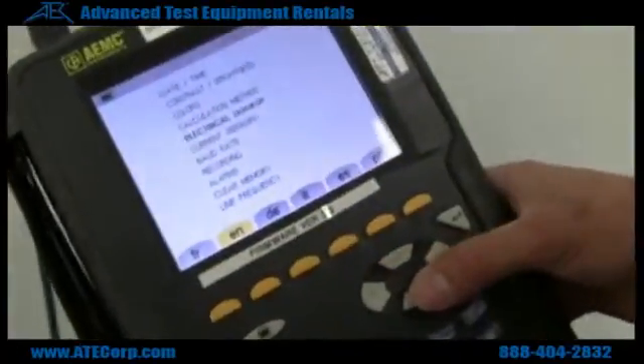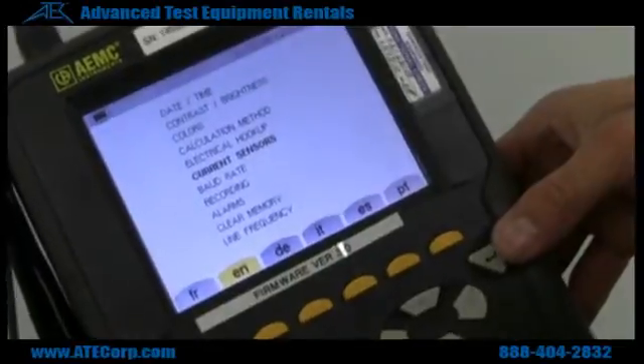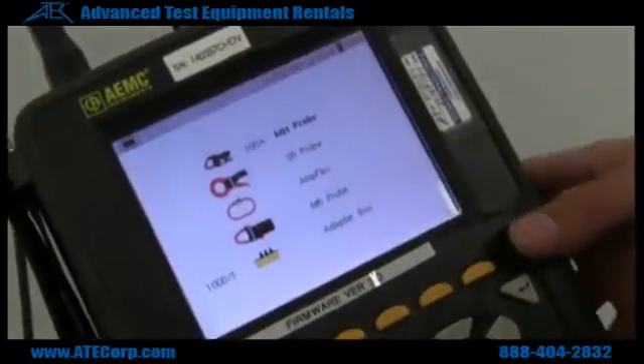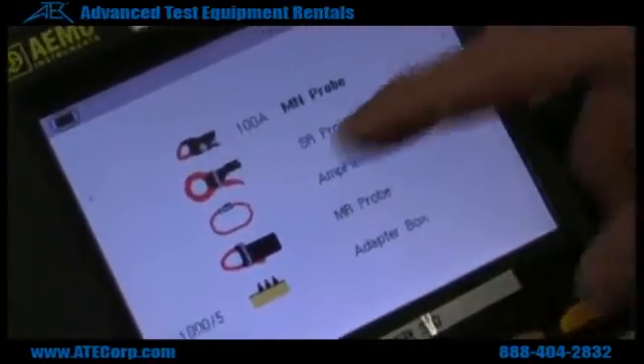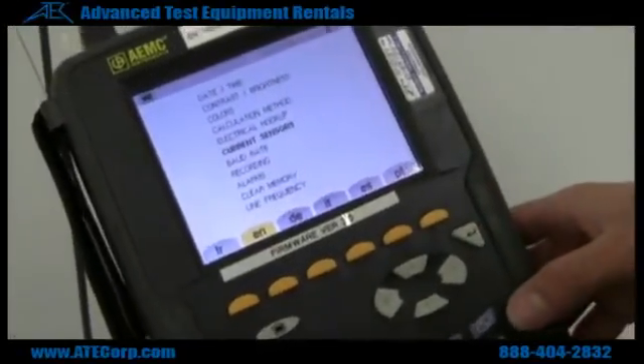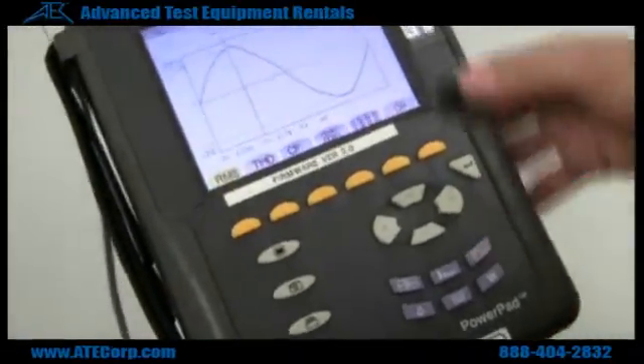After I do my electrical hookup I want to check my current sensors. Most of the time the AEMC 3945 recognizes what current clamp you have on it, but just to make sure you always want to check. In this case we have the MN probe, and we have it set for the 100 amp range, and it's highlighted so I have the correct setting on here right now. I'm going to go ahead and hit enter.